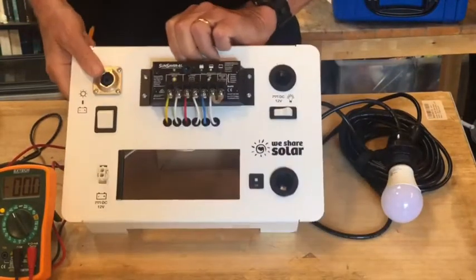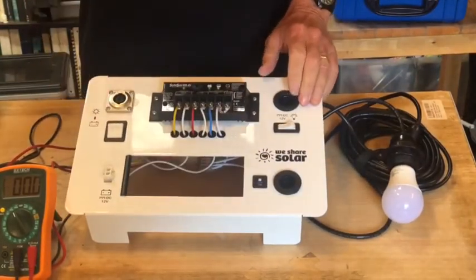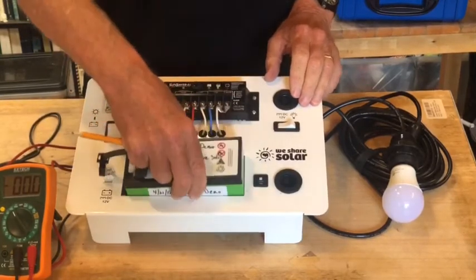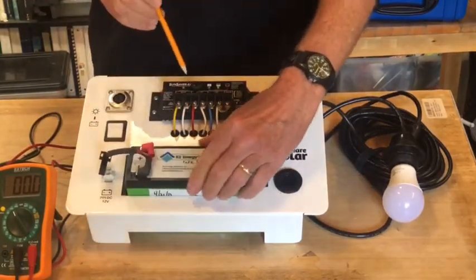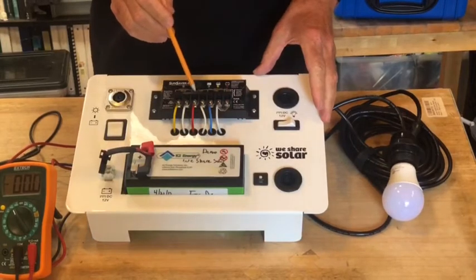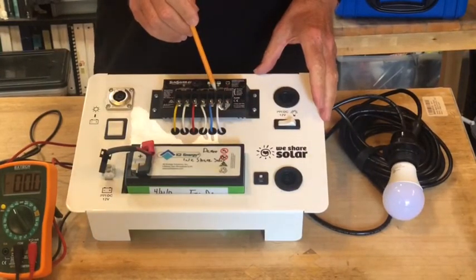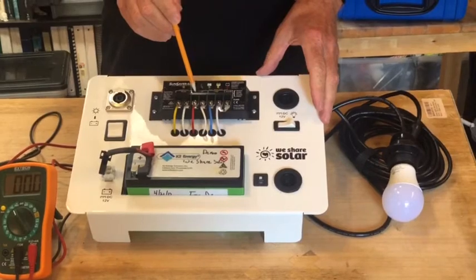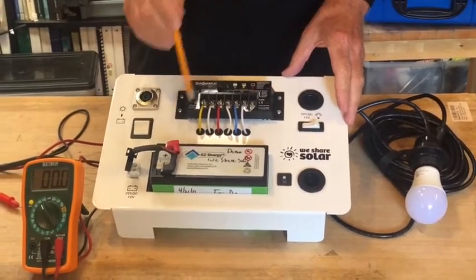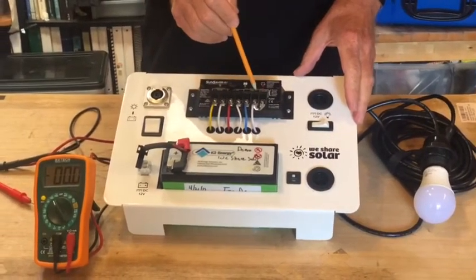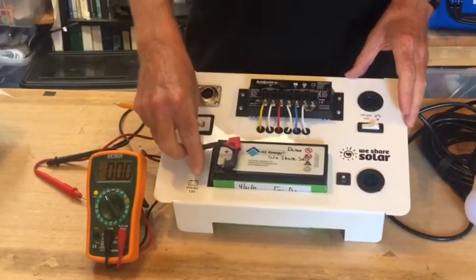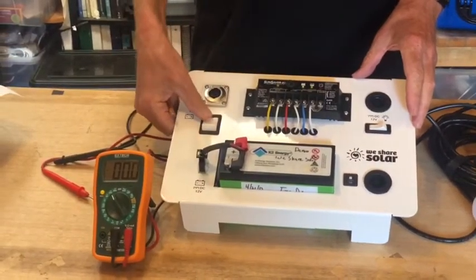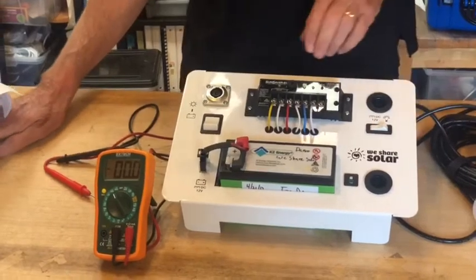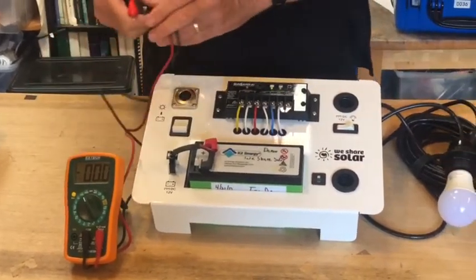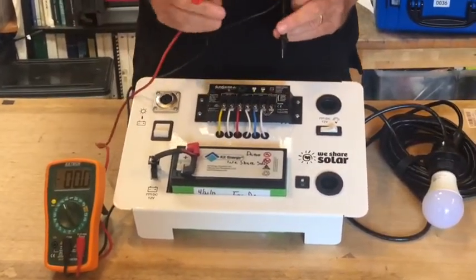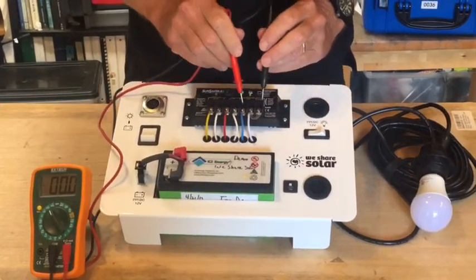Now the next thing we'd check is to make sure electricity is going from the charge controller's battery terminal to the load side of the charge controller, since the charge controller controls electricity going from the battery to the loads. So we plug the battery back in, turn the system on, and use our multimeter to take a voltage reading on the load terminals.